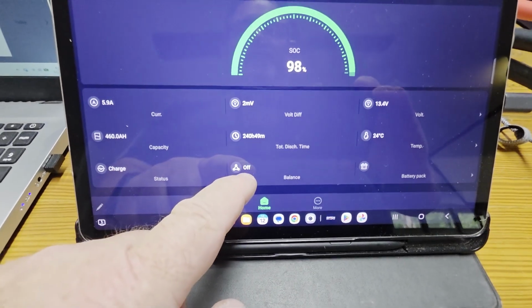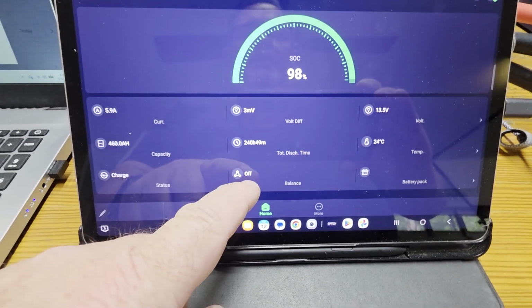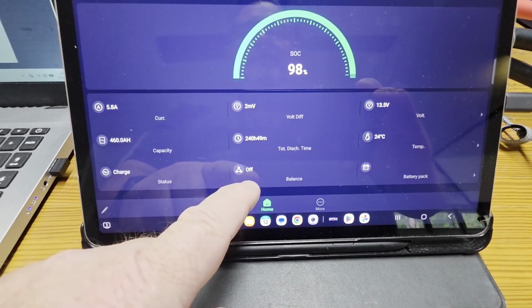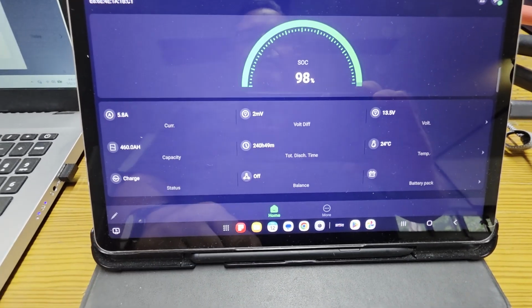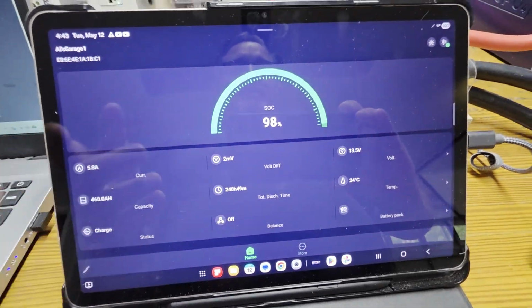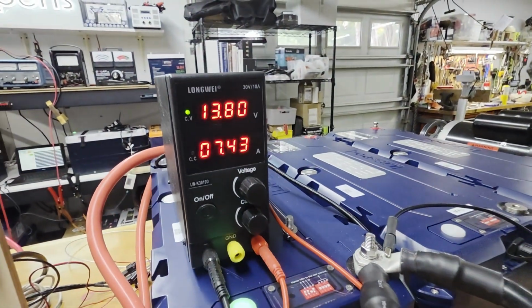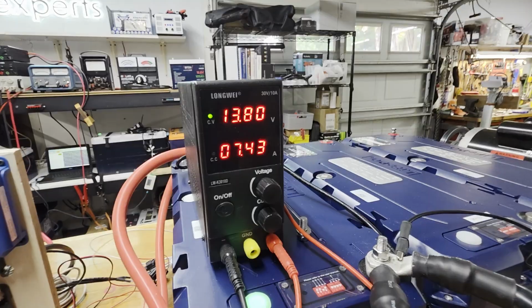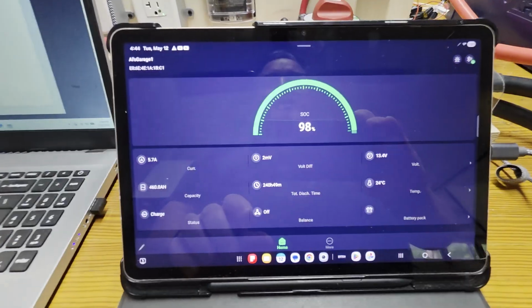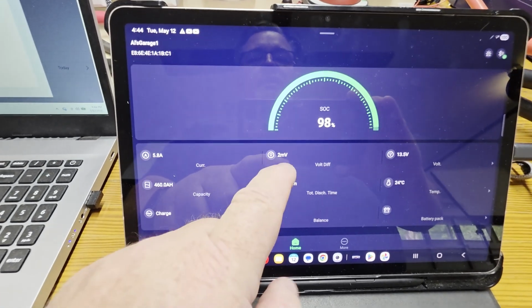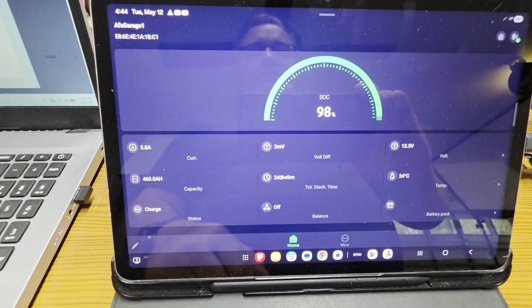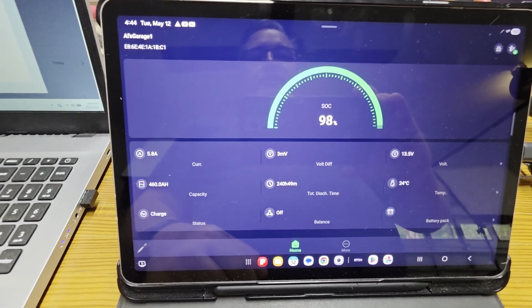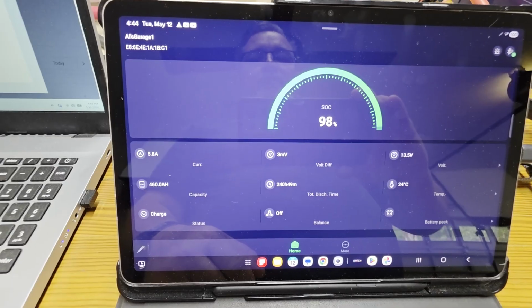If you have the new Epoch Cloud app, you'll see this balance icon right here go to on, and it'll show that it's balancing. From there you just let this sit for 12 hours, 24 hours, even 48 hours, however long you need to let it sit to get this millivolts down below 50 millivolts. Of course we're only reading 3 right now, but if this was a brand new battery you might see more.